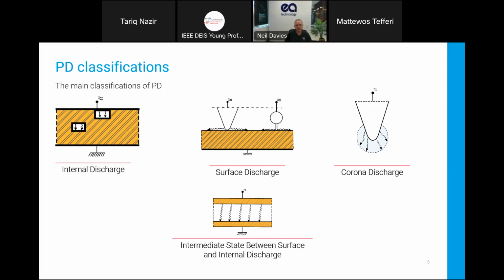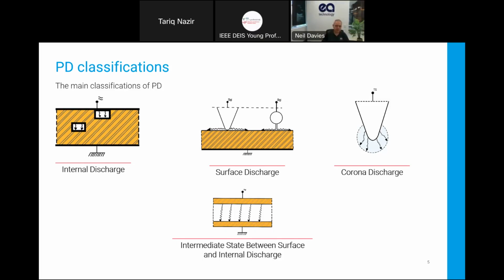So internal discharge is often characterized by quite high amplitudes of discharge and a relatively low repetition rate. So you'll get a buildup of stress across that cavity, and then it will effectively break down like a capacitor breakdown, and that will give you a burst of energy. So it will happen 1, 2, 3 pulses per cycle on the rising and falling edge of the sine wave. So quite high energy, relatively low repetition.